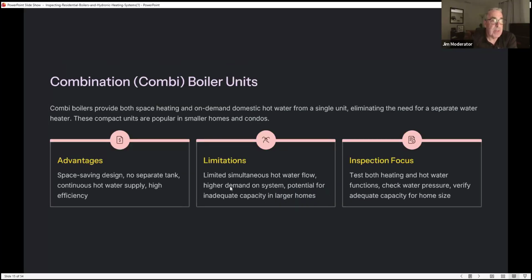Combination combi boiler units. Combi boilers provide both space heating and on-demand domestic hot water from a single unit, eliminating the need for a separate water heater. These compact units are popular in smaller homes and condos. Advantages: their space-saving design, no separate tank, continuous hot water supply, and their high efficiency. The limitations: limited simultaneous hot water flow, higher demand on the system, potential for inadequate capacity in larger homes. Inspection focus: test both the heating and the hot water functions, check the water pressure, verify adequate capacity for the home size. That's a little difficult to do during the inspection.